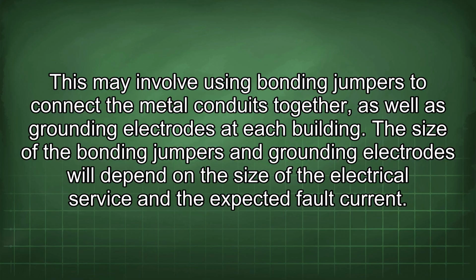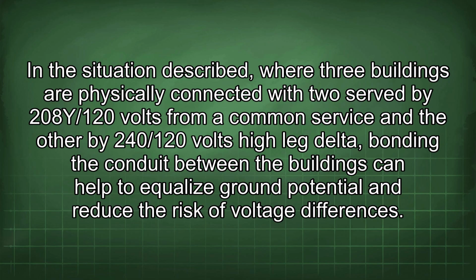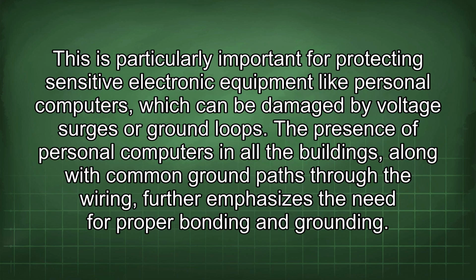In the situation described, where 3 buildings are physically connected with 2 served by 208Y/120 volts from a common service and the other by 240/120 volts high leg delta, bonding the conduit between the buildings can help to equalize ground potential and reduce the risk of voltage differences. This is particularly important for protecting sensitive electronic equipment like personal computers, which can be damaged by voltage surges or ground loops.